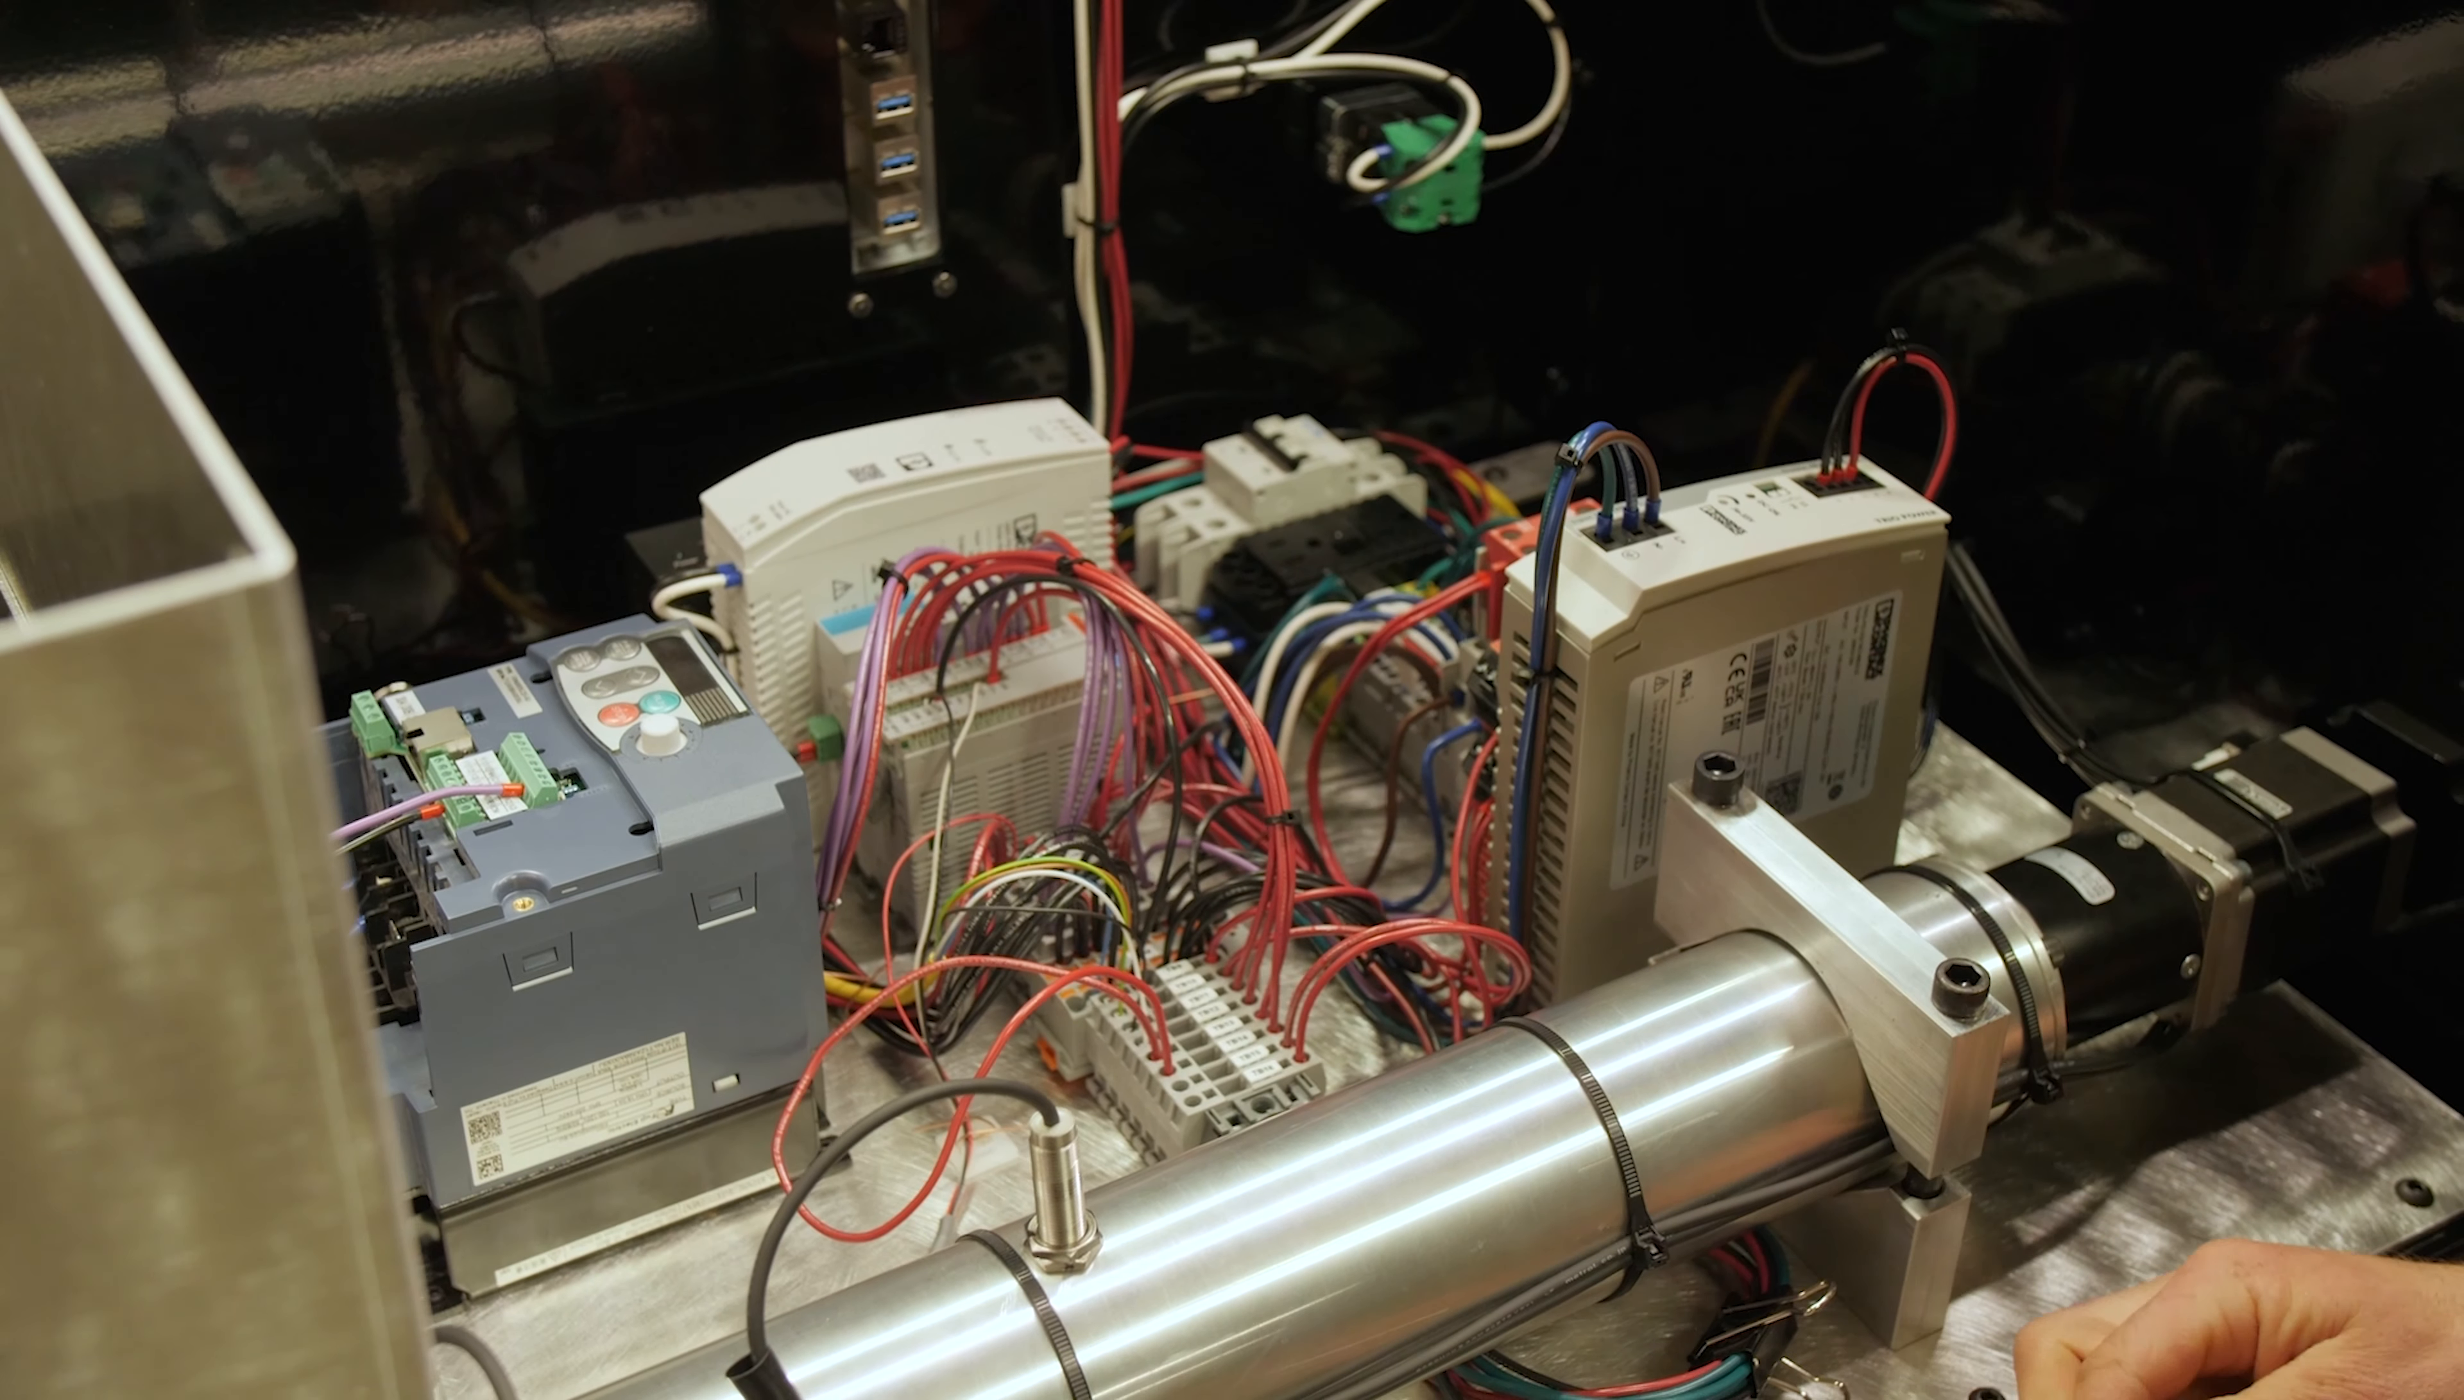Hi, I'm James from Morehouse. I'm here to demonstrate our automated force calibration system. I've got it hooked up to a 30,000 pound Morehouse UCM. We've got a 10,000 pound cell in tension and a Morehouse 30,000 pound reference cell. We're really looking forward to seeing this in action today.